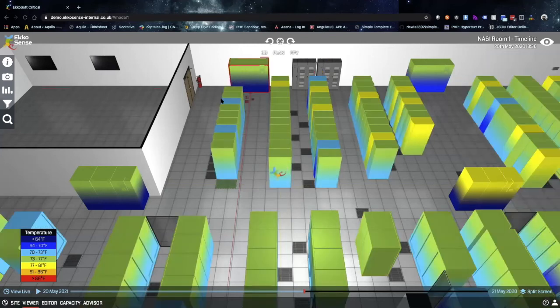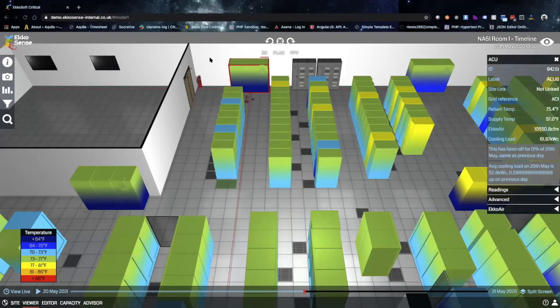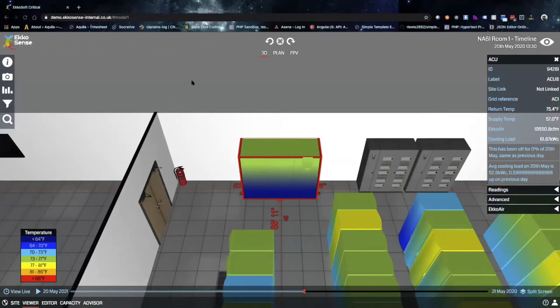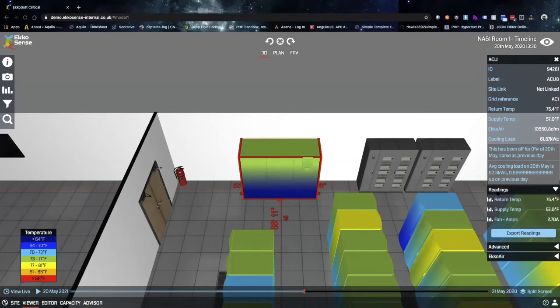And then just like the racks, if we want to take a look at an AC unit, all we have to do is click on it, and we'll go ahead and click the target again so we make sure we're looking at the correct one. Then we'll just get some general information up first. So grid reference, return temperature and supply temperature, the total CFM currently, as well as the cooling load. And then we can dive further into the readings, so the return temp, the supply temp, as well as the fan amperage.